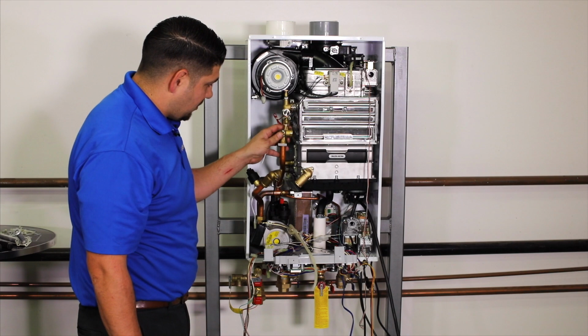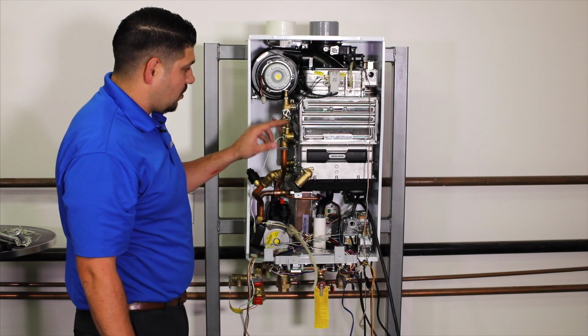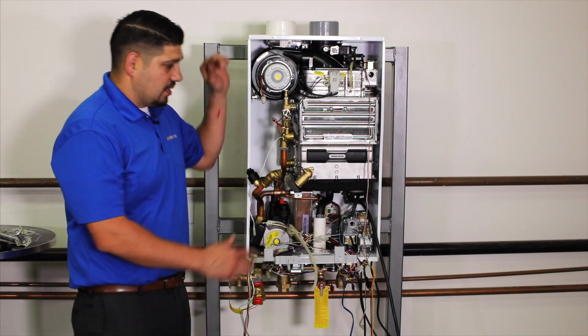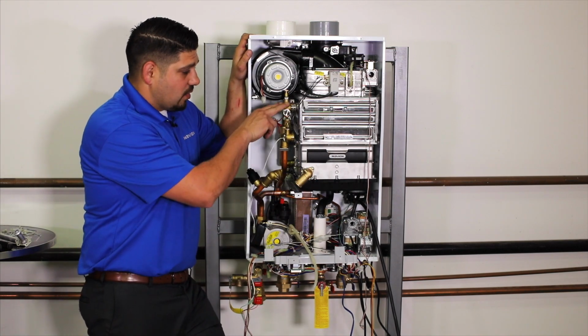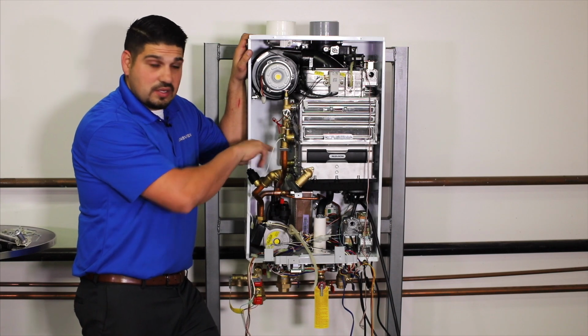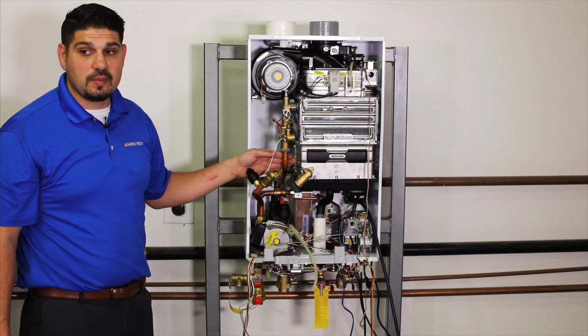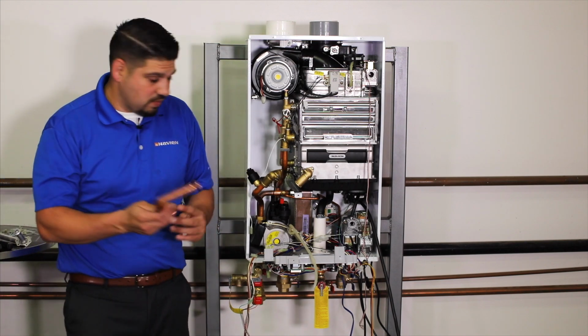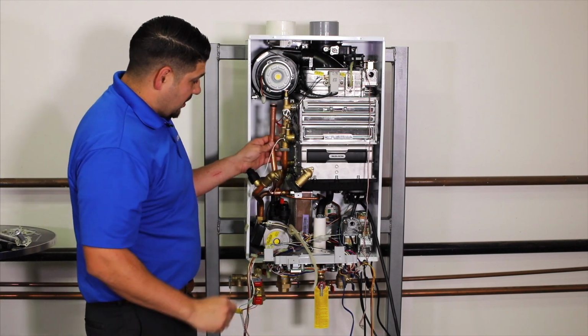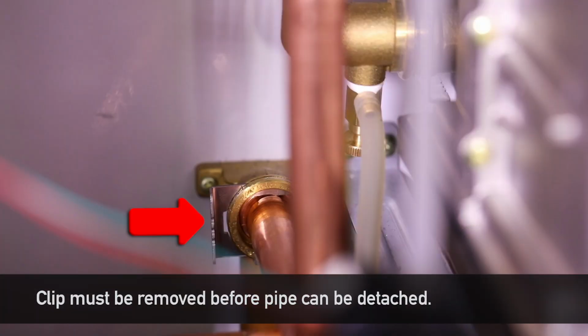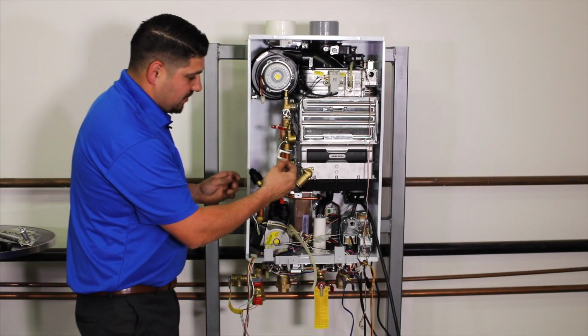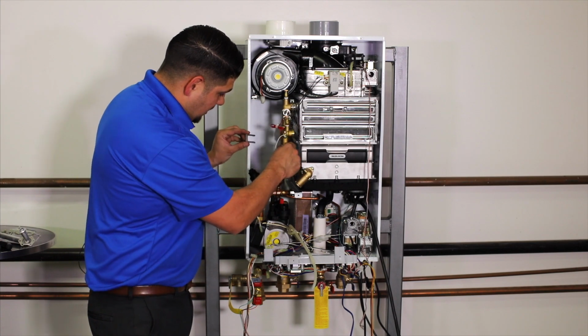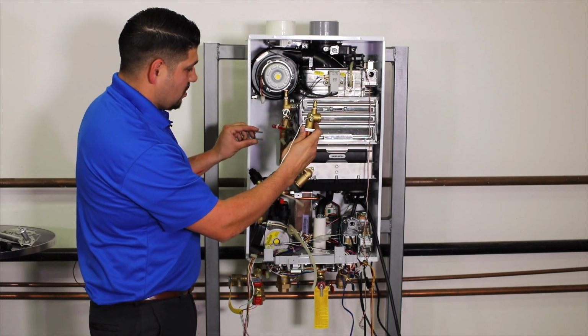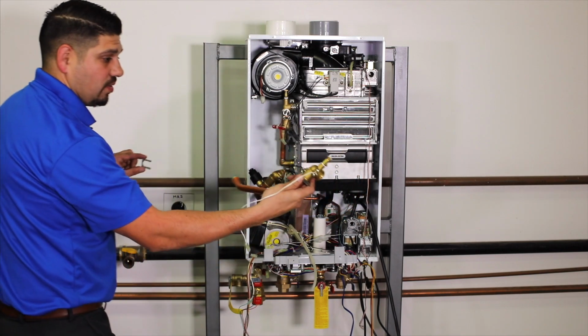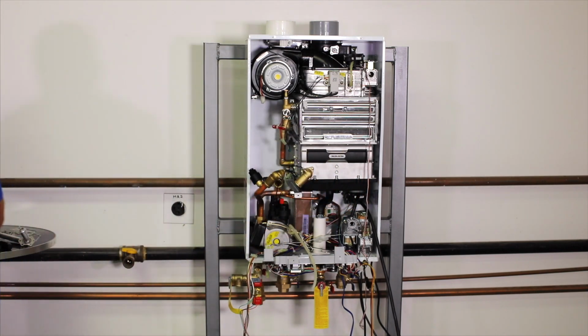So just as an example here, what we got here is the outlet of our old heat exchanger used to be down here. The new design of the new heat exchanger, we've relocated it. So this plumbing, this tube that goes down right along the side of your heat exchanger is not going to work anymore. So what we're going to have to use is the new tube provided for us. It's going to go right about there. I'm going to slide this clip out, and that's all that's holding our old pipe in. So pulling our old elbow and pipe, I'm going to remove that.